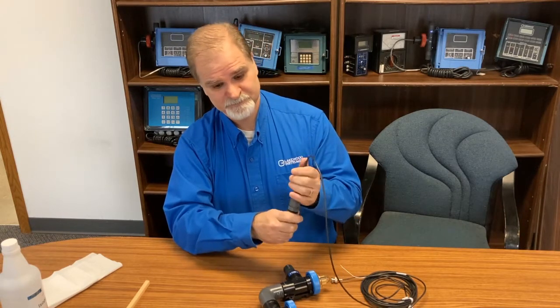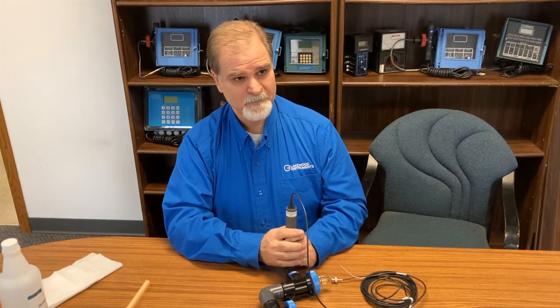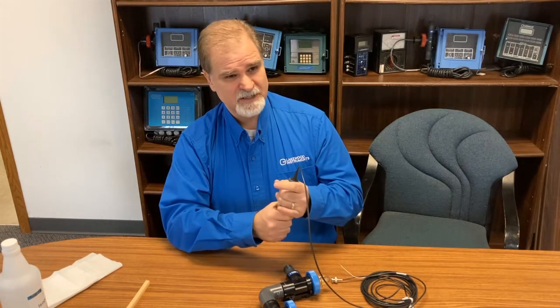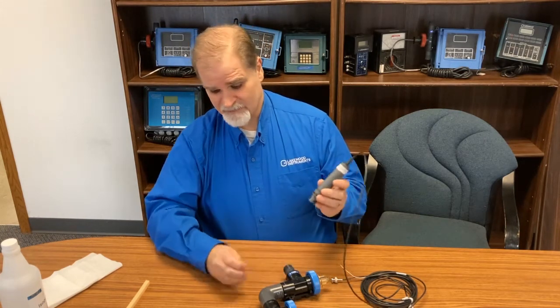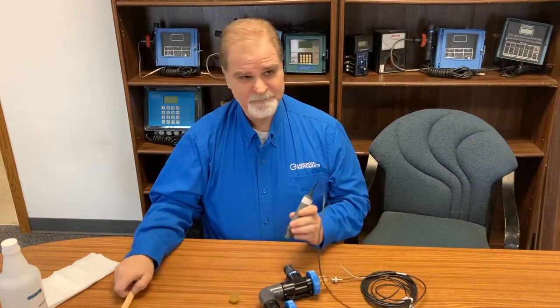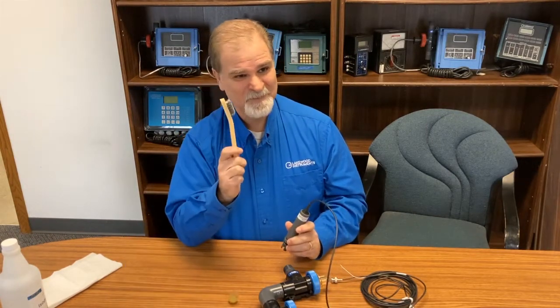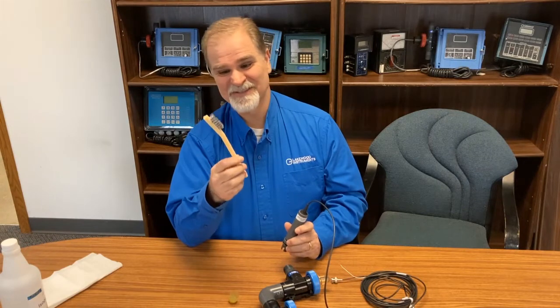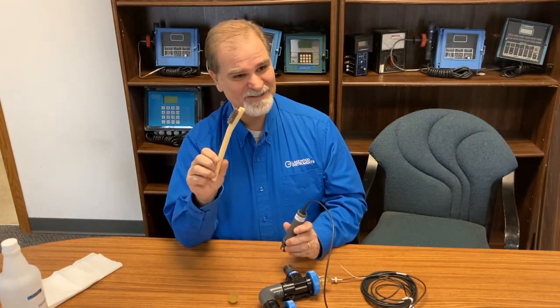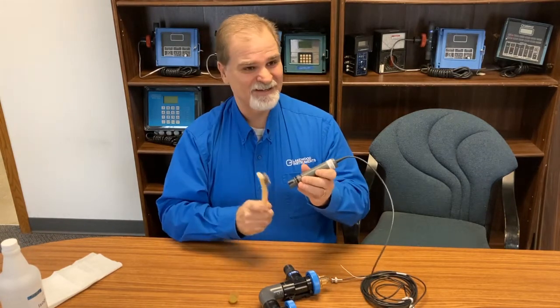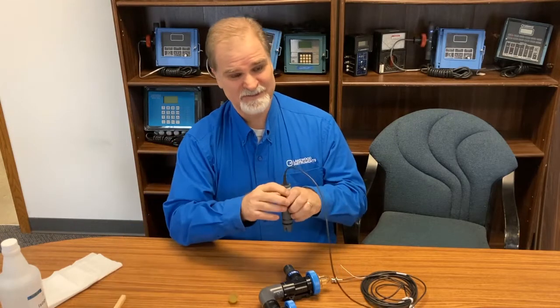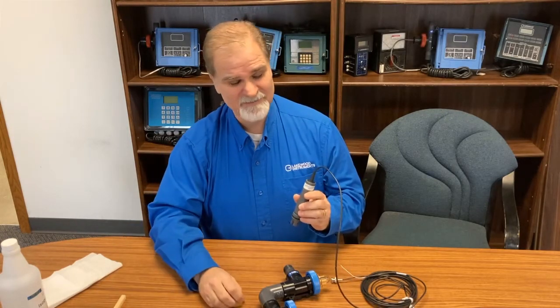Now, you said that pH sensors can be fouled, so they can accumulate scaling and all kinds of other things too, right? Scale or biologicals will foul them, so you have to keep them clean. And I see you got a wire brush there, so you should take that and go at it, right? No, sir. This is the one thing you should not use on pH and ORP glasses. Do not scrub on that glass.